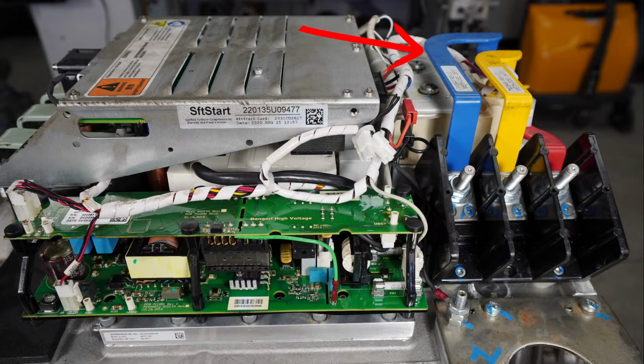Now, typically in my experience, an SCR when it fails will usually short internally. And that's going to cause blown fuse issues. You're going to have main power issues when you lose an SCR, typically. But that is not the only way they can fail. Sometimes they can fail where they're just essentially open, and they're just not passing anything through.